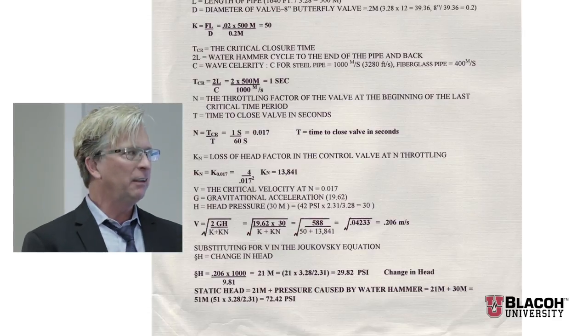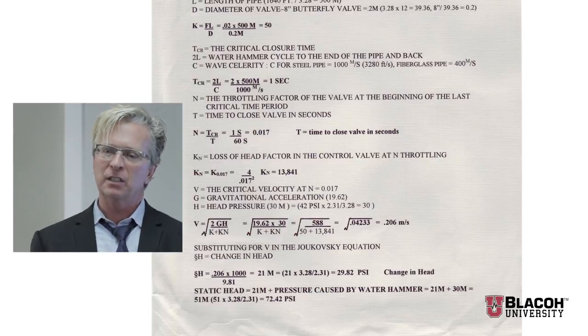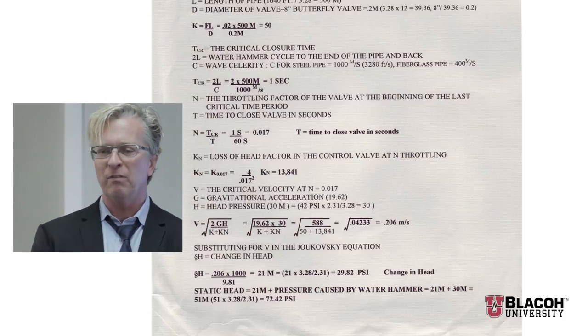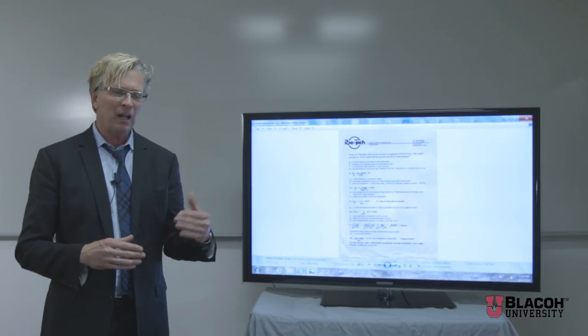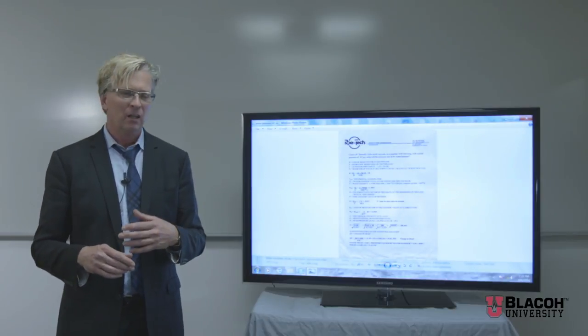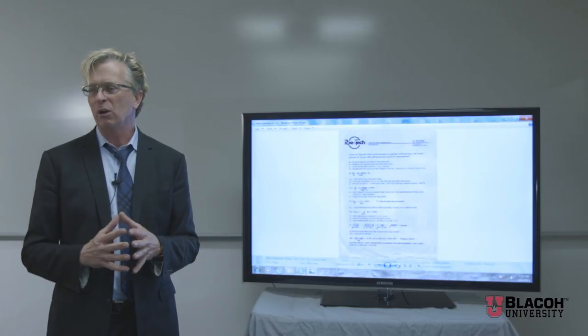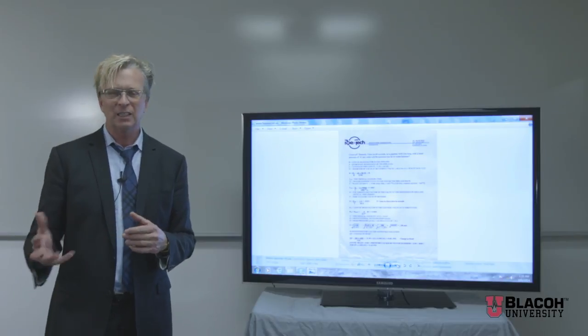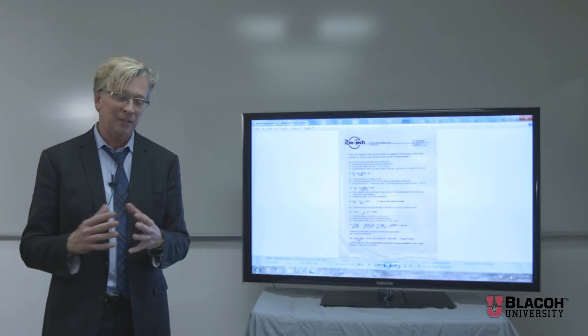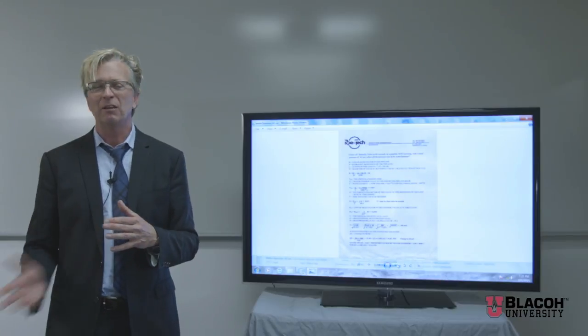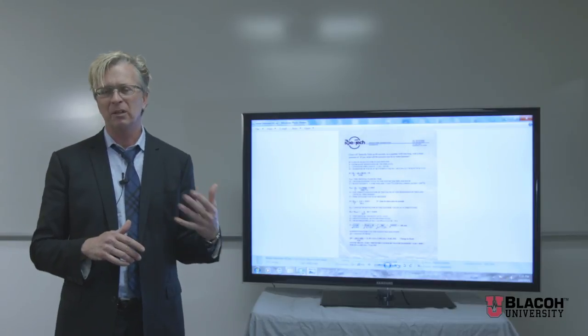The next example is almost exactly the same except we change our closing time to 60 seconds, slowing that change in velocity down. We find everything being the same except the time step. The pressure before at 20-second closure was 129 PSI, now the increase in pressure is 72 PSI.